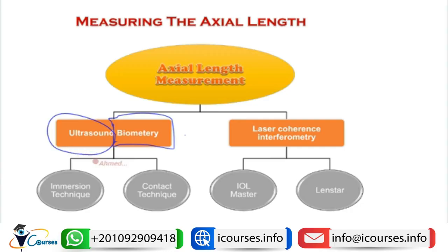Different methods can be used for ultrasound biometry, like the immersion technique and the contact technique. And there are different devices that use the laser coherence interferometry principle for measurement of the axial length, like IOL Master and Lenstar.